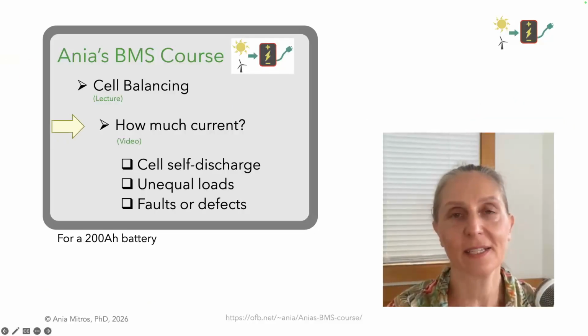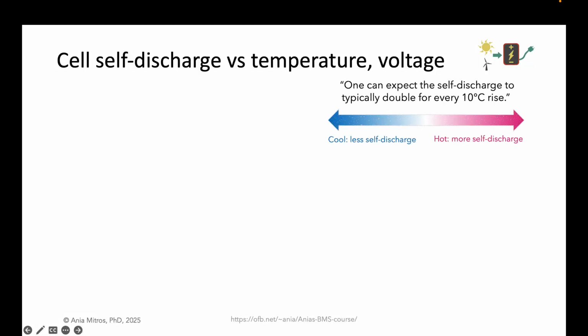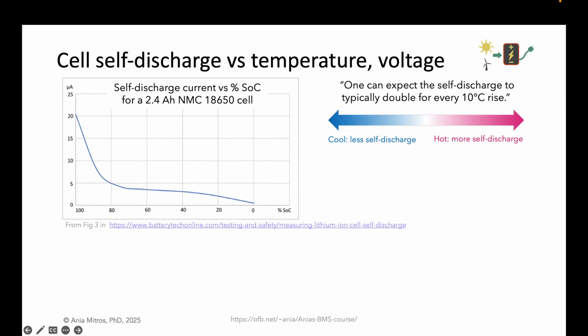Let's look at cell self-discharge. Cell self-discharge increases with temperature and is substantially higher at high state of charge than at low state of charge. This is kind of nice in that a nearly empty battery depletes itself more slowly than a fully charged battery. Here's a curve for one battery's self-discharge as a function of state of charge, and from the same source, an estimate of self-discharge with temperature.